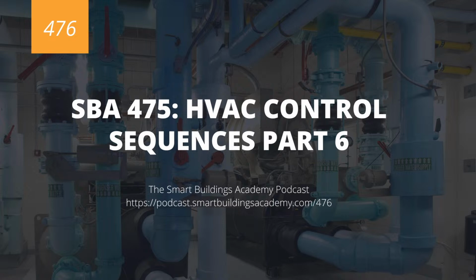Now, this is optional, but it's not optional. So what I mean by that is some chillers will command their own valve. I'm highly hesitant to let chillers command their own valve, to command their own pumps. Maybe I'm just a control freak, but I like to have control of those. So once the chilled water system is enabled, the isolation valves on the chiller should be commanded open by your control system. This should be the first thing you do.